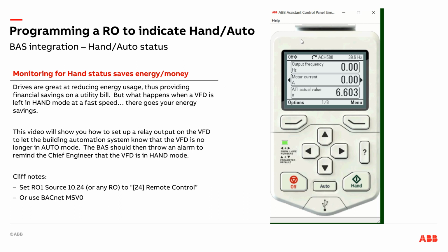And then, oh, by the way, for all the controls contractors out there, don't forget to throw an alarm in your automation system when you see that the drive is in hand mode to kind of remind the chief engineer, the folks in charge of the facility that, yeah, the drive's in hand.